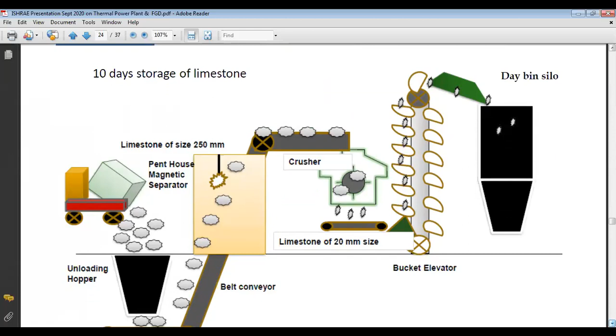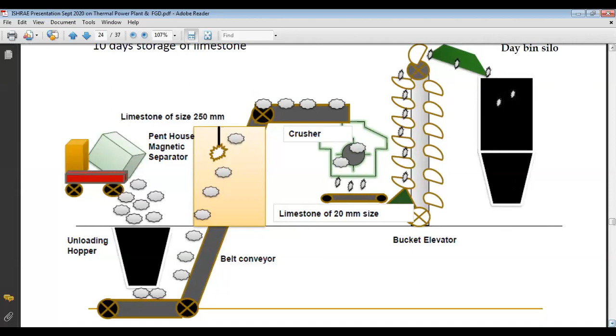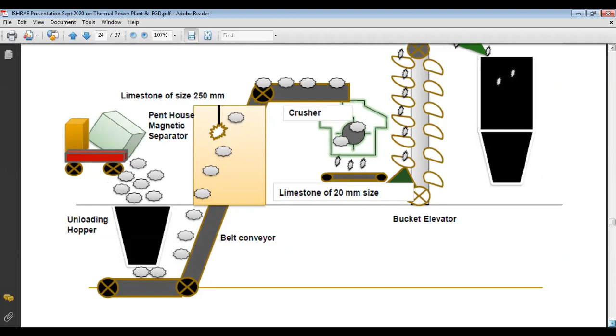Basically, limestone is found in lump sizes like 250 mm, and the limitation of the grinding mill is that it will not allow limestone beyond the size of 20 mm. So for that reason, we have to install a crusher also. From the crusher, it is crushed to a size of 20 mm. From there it is fed to the day bin silo, and from this day bin silo, it is further fed to the ball mill, where grinding takes place and the slurry formation takes place, and that slurry is again sent to the absorber.